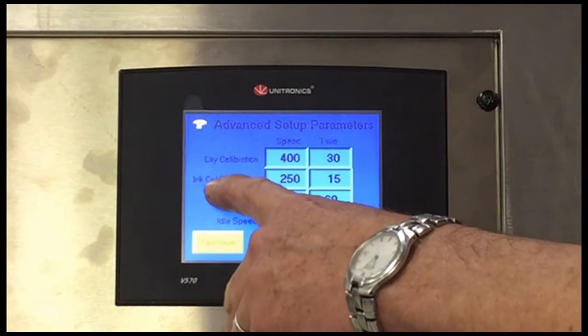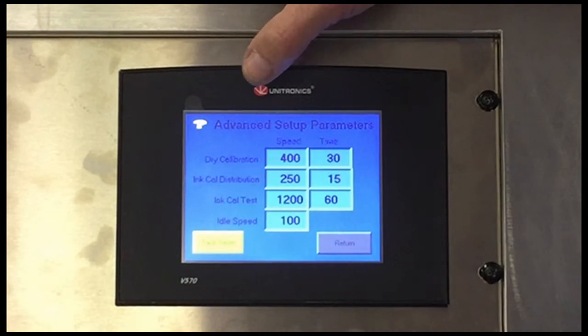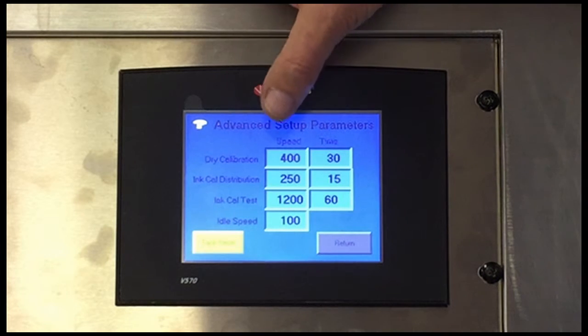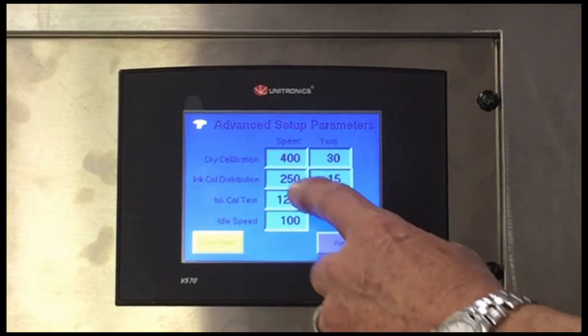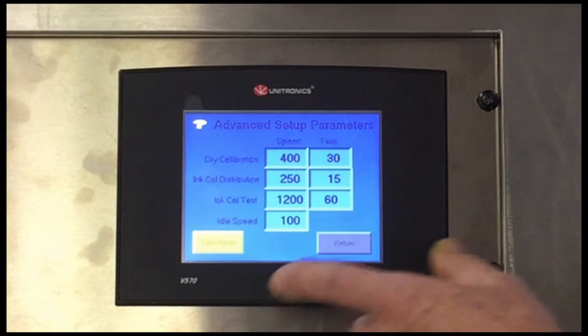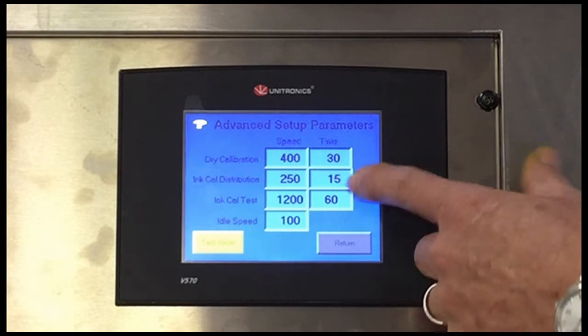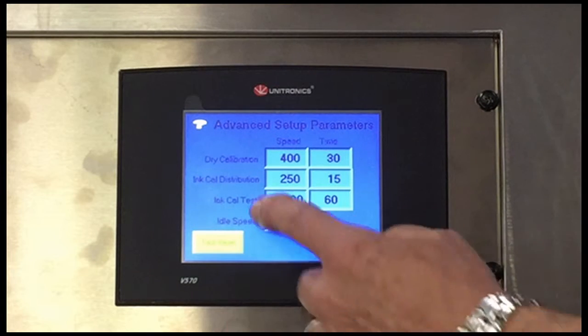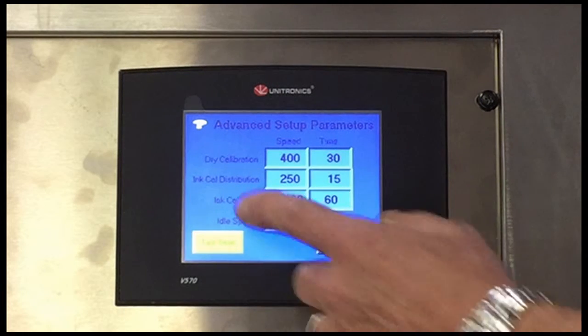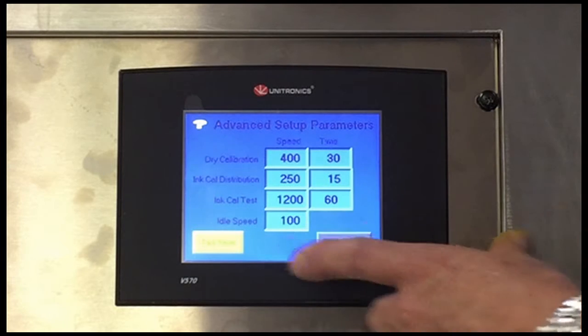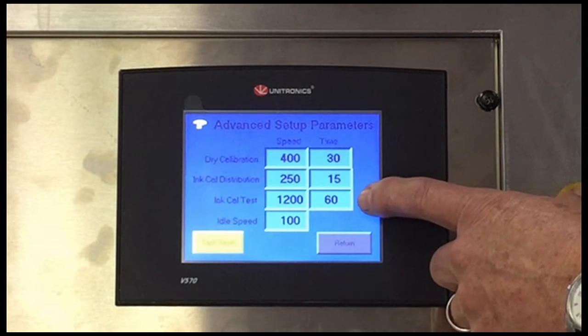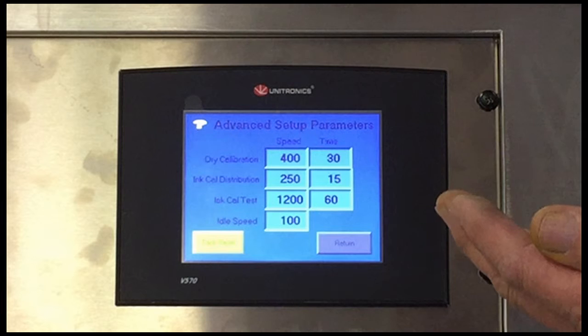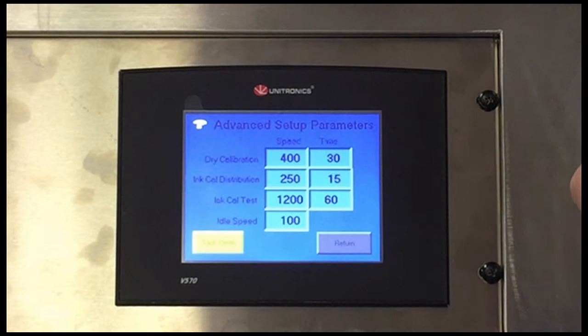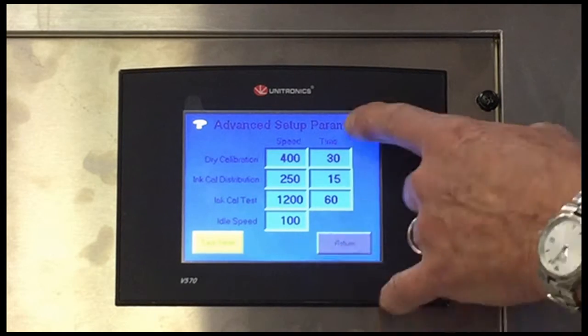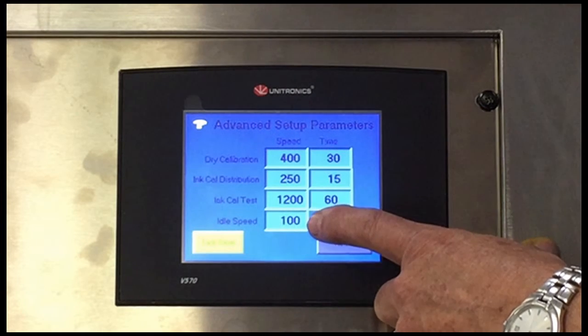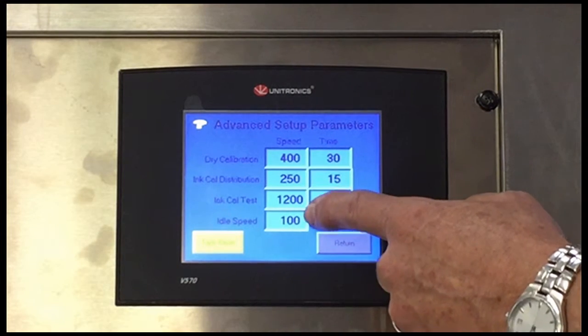The second line here is for the ink calibration. When we do a wet calibration, which we are actually going to do using an ink sample, we're going to distribute the ink at 250 RPMs for 15 seconds. Again, this is almost like the automatic test. We're going to do our actual ink calibration at 1200 RPM, and we're going to wait 60 seconds before we enter that data because the tack standard is usually a 60-second test. So that's where we're going to want to do our calibration. And then when we're all done, our idle speed is going to go back to 100.